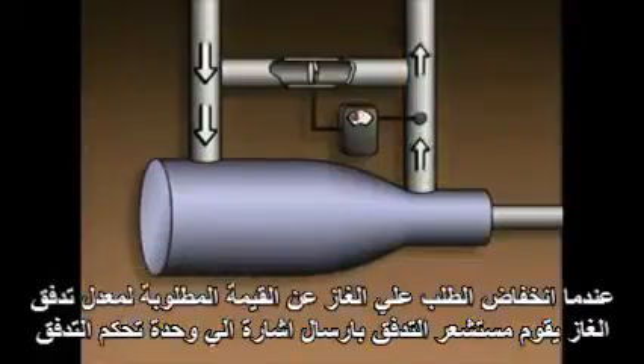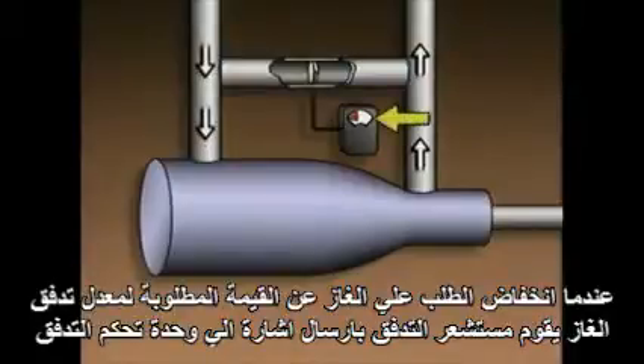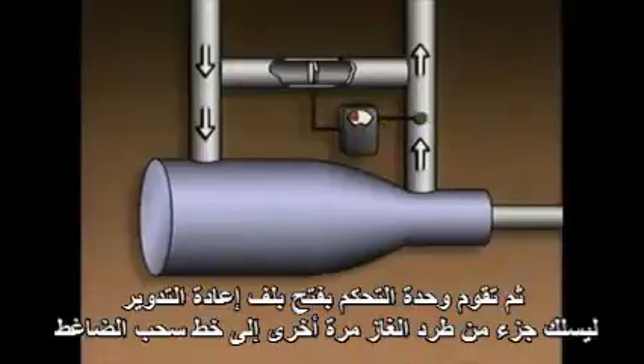When low demand causes the gas flow rate to approach the surge point, the flow sensor sends a signal to the flow controller. The controller then opens the recirculation valve and routes a portion of the discharge gas flow back into the suction piping.